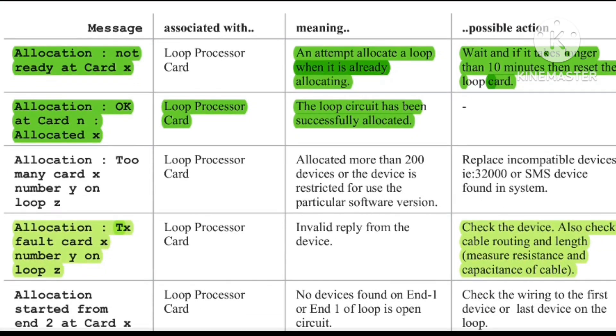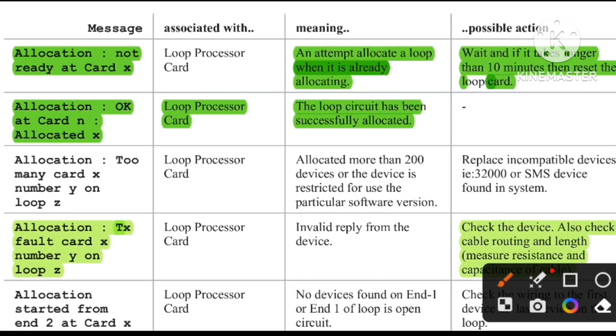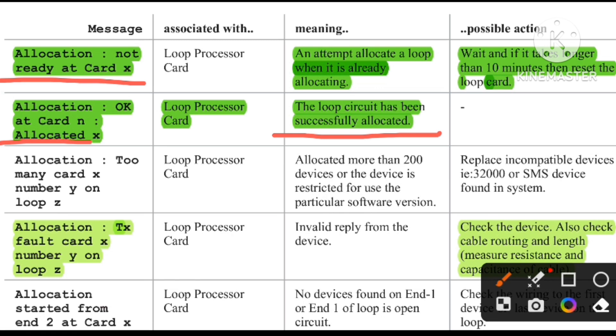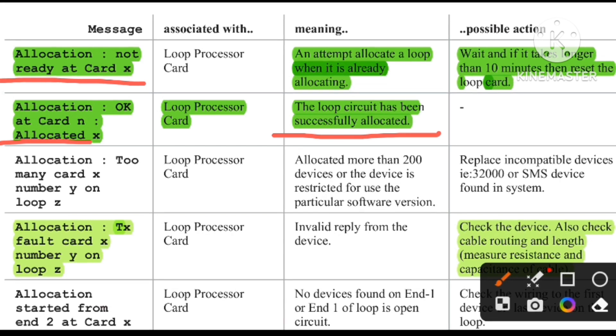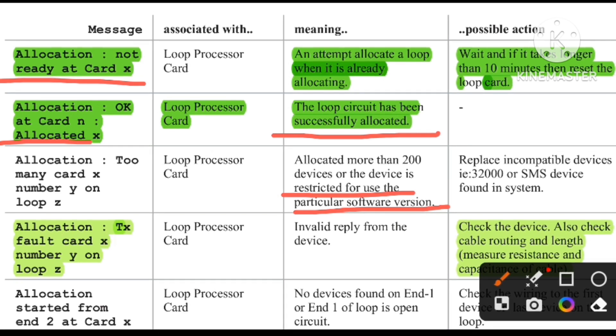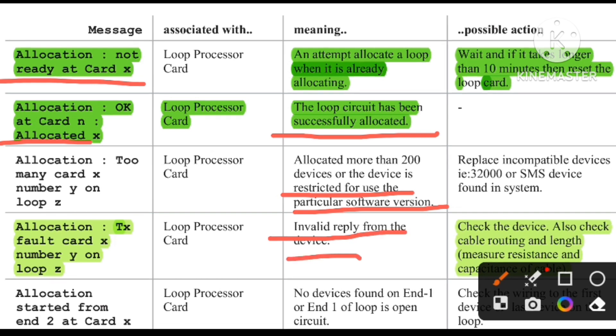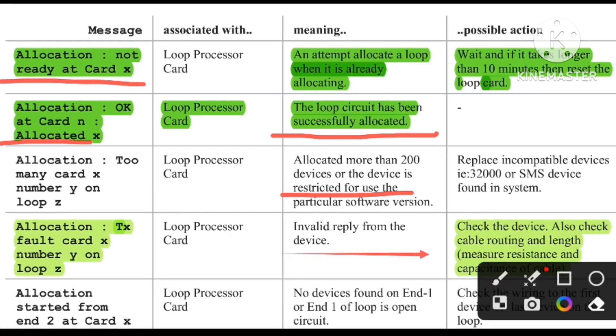Another common fault is 'Allocation not ready at card X' — this means the card has successfully restarted. 'Allocation too many cards' means more than 200 devices are allocated, or the device requires specific software. The most common fault I want to highlight is 'Allocation TX fault' — this means no reply is coming from the device, indicating a loose connection.